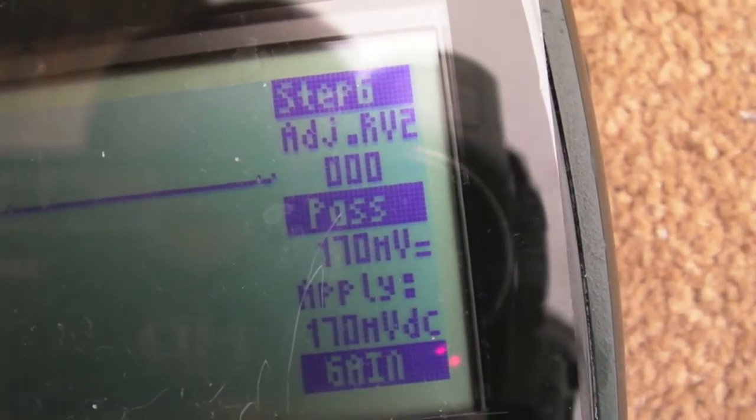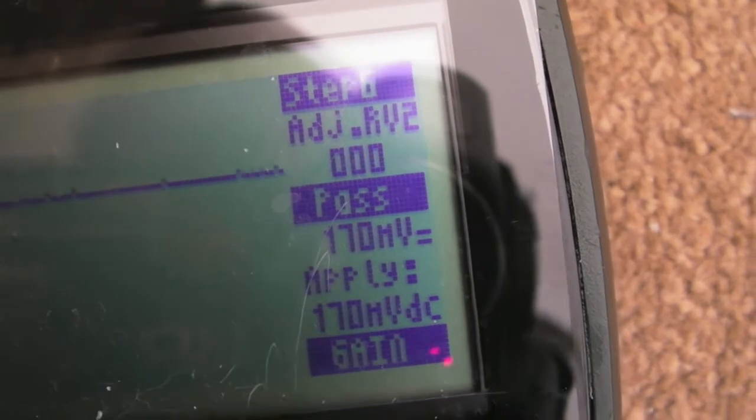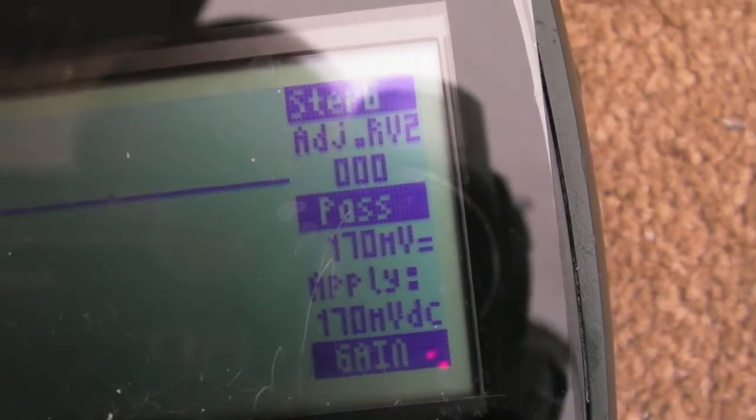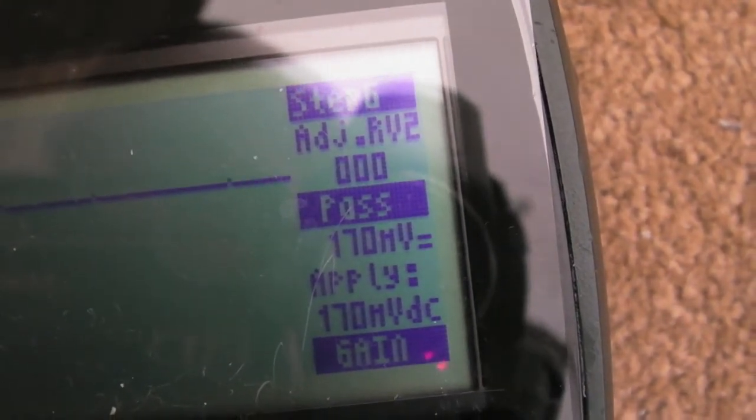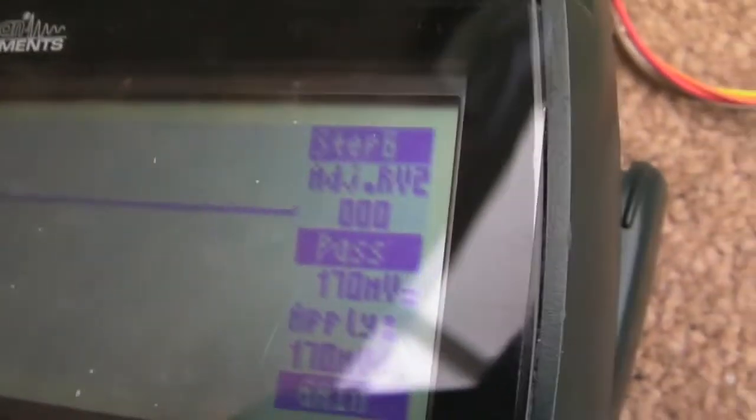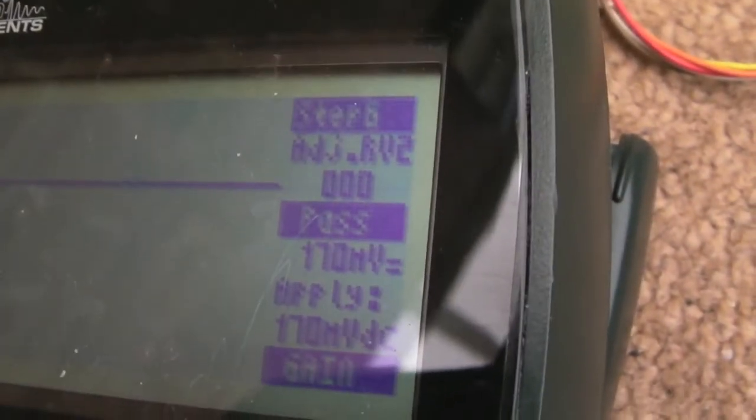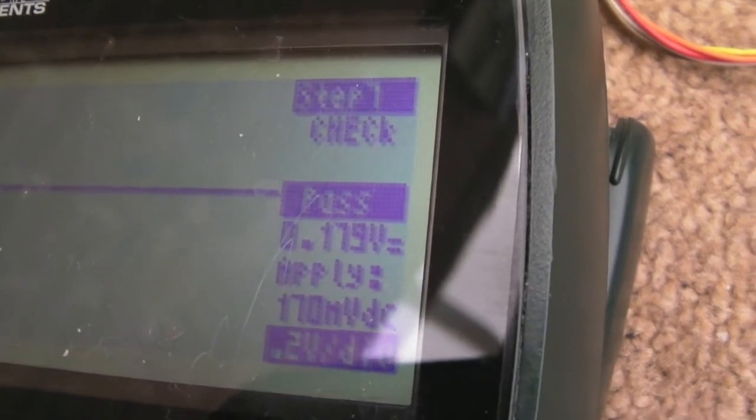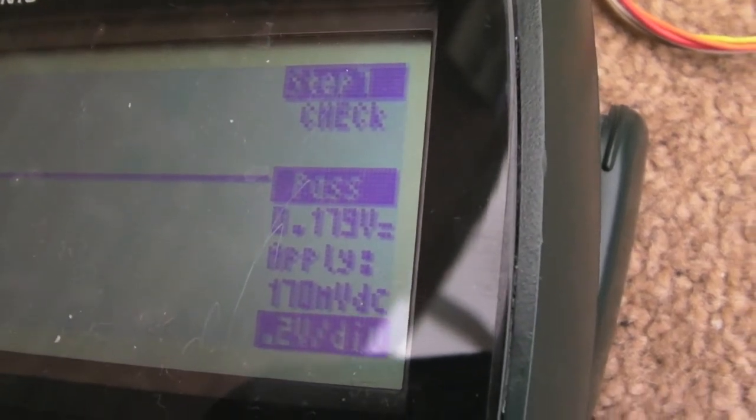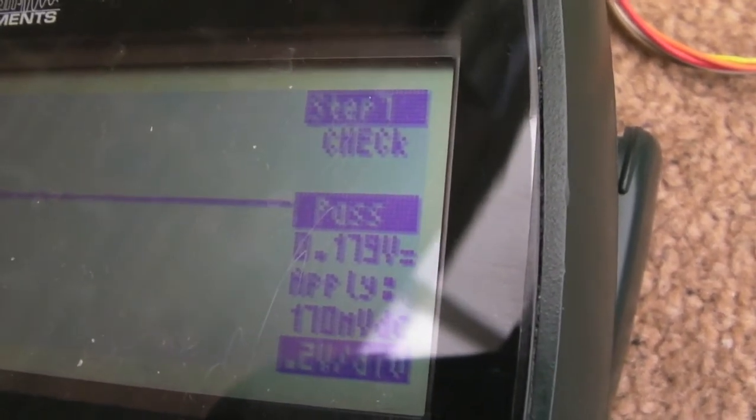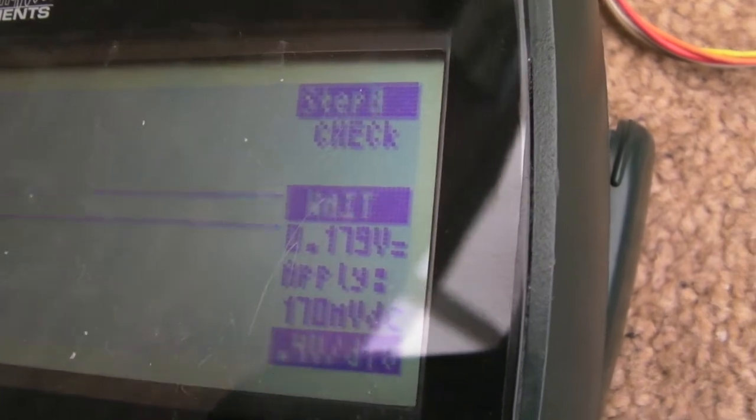So I did the smallest adjustment there to that RV2 and you can see it's now showing 170 millivolts. The meter is just a tiny, tiny touch above, but it's a lot more accurate than it was. Sorry, that glare is awful. Yeah, so that particular test has passed. So click the next button. Yeah, apply 170 millivolts. That's passed in.